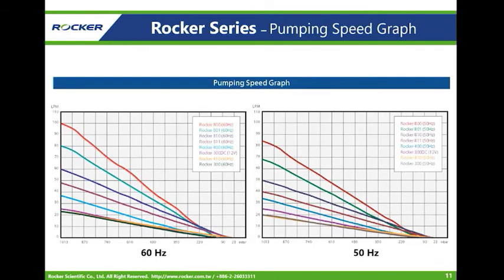Here is the pumping speed graph of the Rocker series pump. In some situations, users need to fix the flow rate, and with this graph, you can find the corresponding vacuum to get the desired flow rate. For example, with a Rocker 800 at 60 Hz, if you want a flow rate of around 70 L per minute, find the Rocker 800 line, locate 70 L per minute on the graph, and you can read off the corresponding vacuum of 740 mbar. So you can achieve a flow rate of around 70 L per minute by regulating the vacuum to 740 mbar.